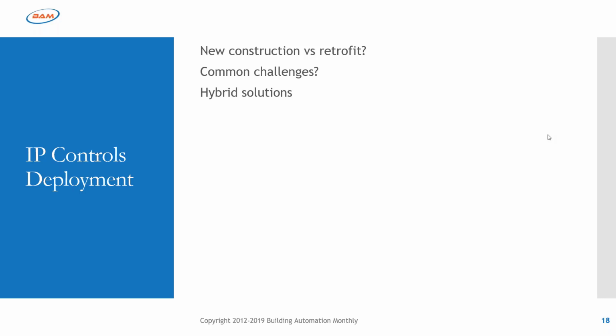It is IP. All of those things I just described, fiber, Ethernet, wireless, 5G, can all be delivery mechanisms, transport mechanisms for IP traffic. So with fiber, you could route multi-mode or single mode into a converter and plug it right into a switch port. You'd be perfectly fine. It's just converting the signaling. That's all it's doing. It's still IP. When you would use that goes back to, you use single mode for long runs and you use multi-mode for short runs. Fiber is not really needed with IP controls because we don't have a lot of data going across our trunks to require that.